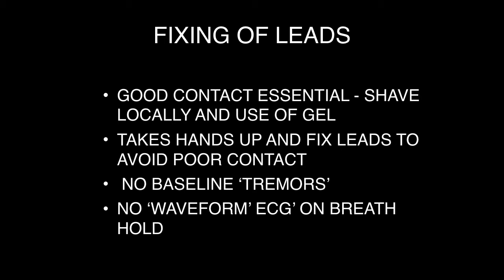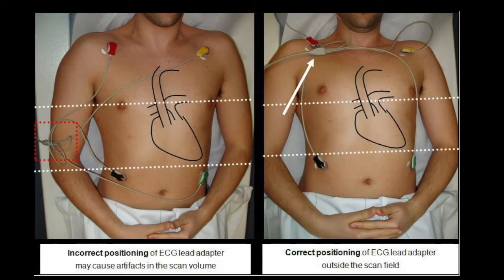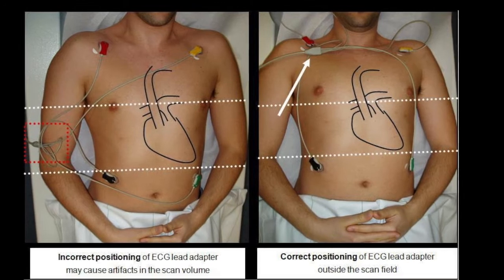Once the leads have been placed, look at the ECG trace on the monitor. No diagnosis needs to be made from this trace; however, there should be no tremors in the baseline, no waveform abnormalities, and the ECG trace should not move with each breath hold and breathing. This diagram shows how the wires of the ECG leads should be kept out of the scan field, which is very important as they may lead to artifacts during acquisition.